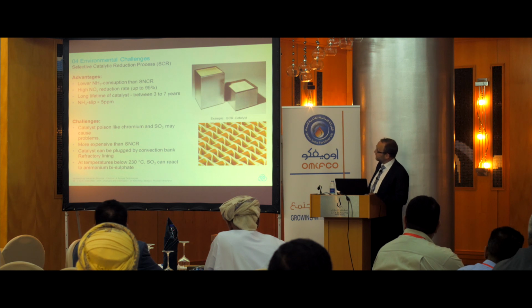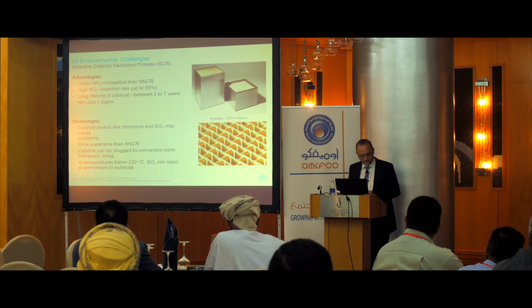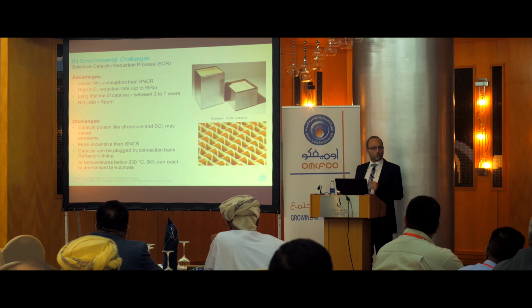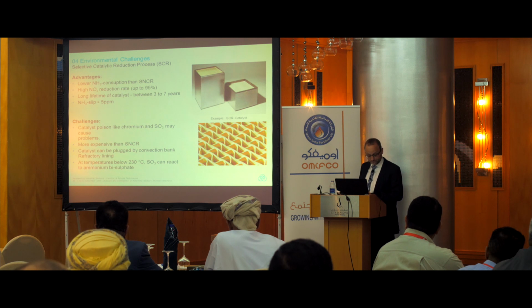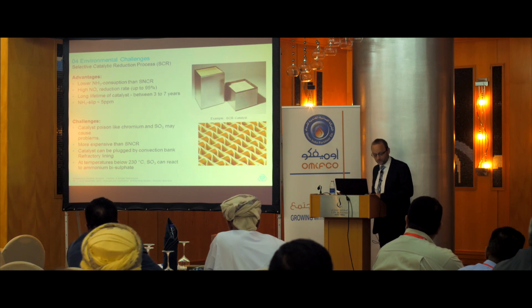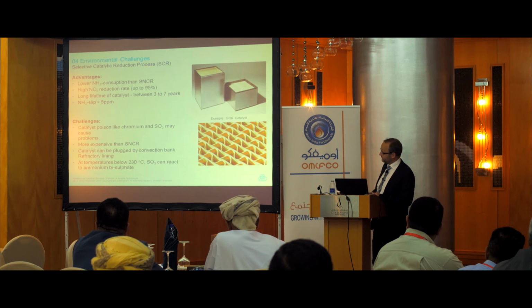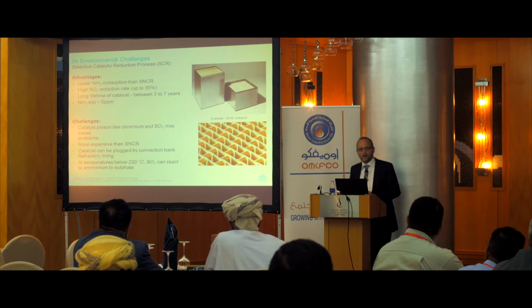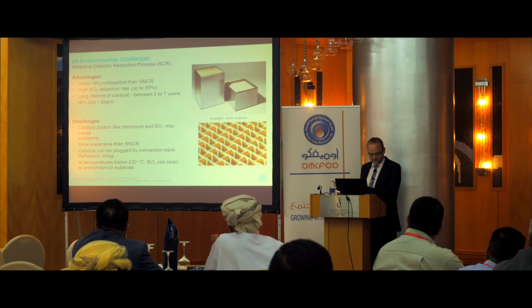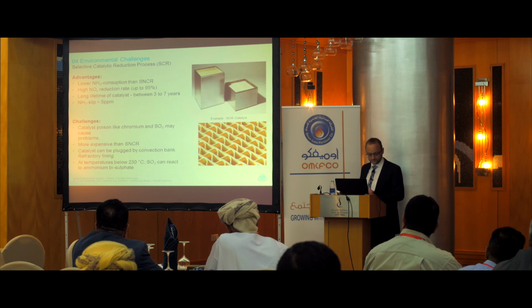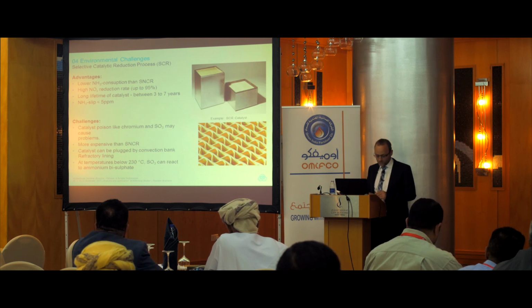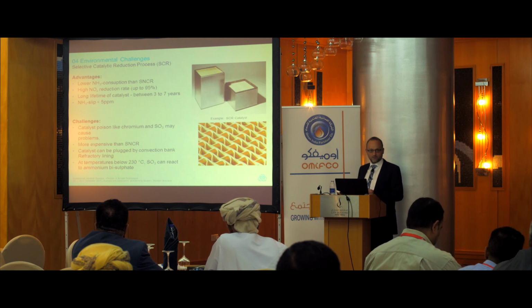The advantages of the SCR, the one with catalyst, is the lower consumption of ammonia water, which is not a big problem for an ammonia plant, but maybe for hydrogen plants it would be a huge benefit. Then you have higher NOx reduction rates, up to 95% for SCR, compared to only 50% for an SNCR system. You still have a very long catalyst lifetime. And last but not least, the ammonia slip at the stack can be less than 5 ppm.